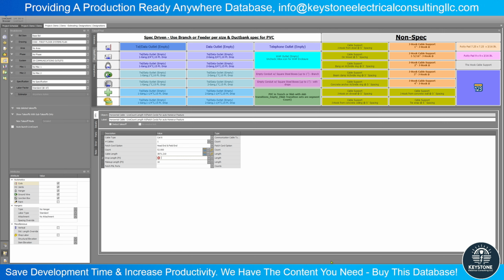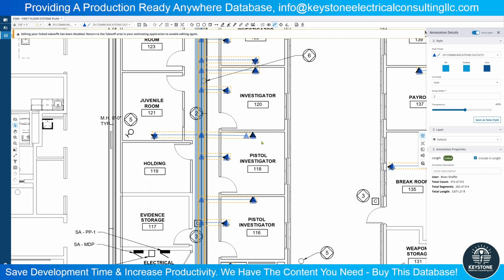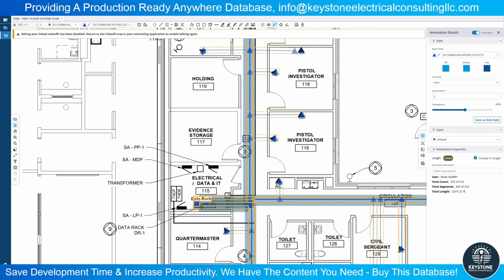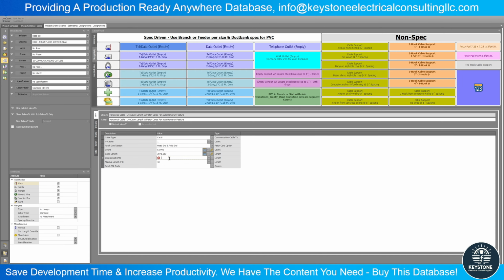So this could be, let's go back here and visualize this. I'm going to go down at this outlet here. So let's say I want 10 feet to go vertical here, and then at the data rack I want to go down there as well. We'll say that is also 10 feet. Going back over here, I'm going to say 20 then, so that's an added length, 10 at the outlet, 10 at the data rack. And then if I want to do something like a service loop or just an arbitrary makeup length, I certainly can do that. So I'll leave 10 there as well. I'll do a 24 port patch panel, and then I can hit OK.